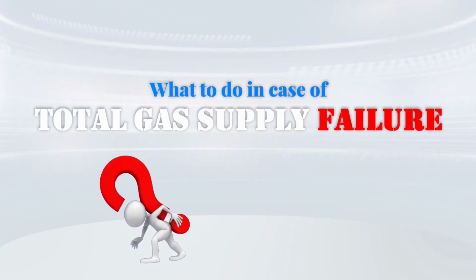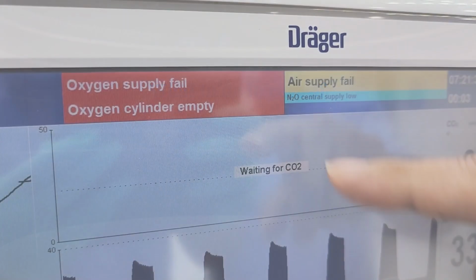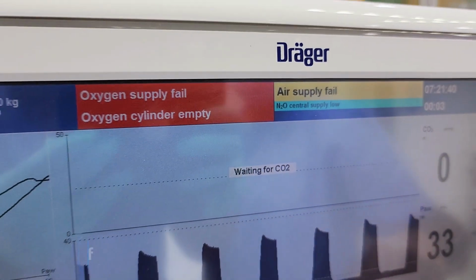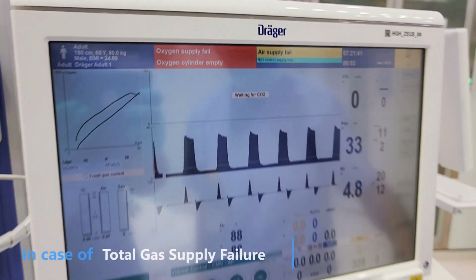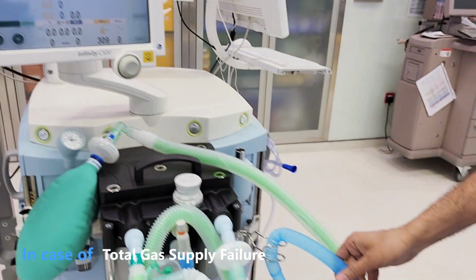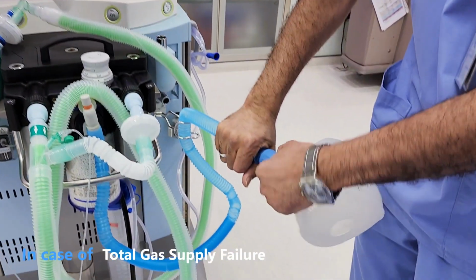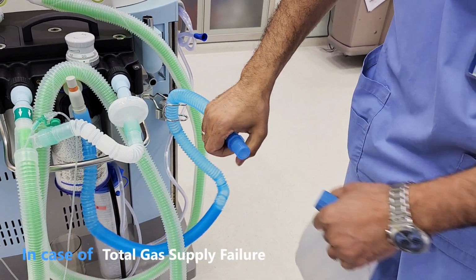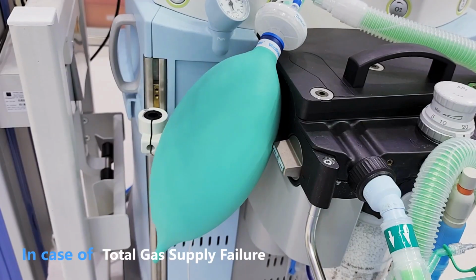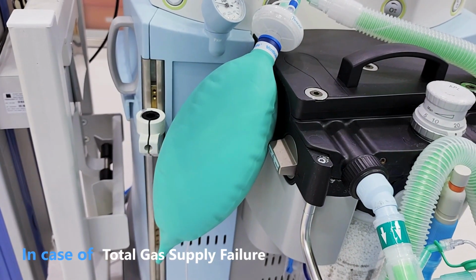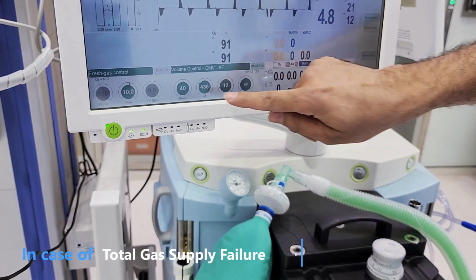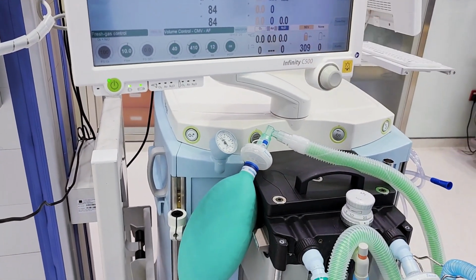In case of total gas failure, no pipeline supply, and the oxygen cylinder is empty, we can still use the machine to ventilate the patient. What we have to do is just remove the reservoir bag. The machine will start to suck the ambient air and start to ventilate the patient with 21% oxygen. You will be able to adjust the flow and ventilator parameters.